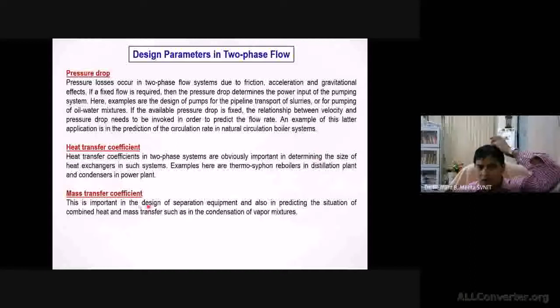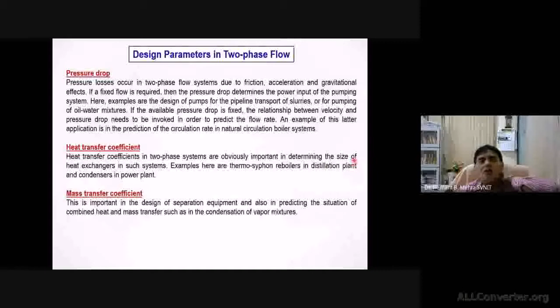The second is the heat transfer coefficient. The heat transfer coefficient for single phase flow and for multi-phase flow are different. The heat transfer coefficient in two-phase flow systems is very important in order to define the size of the heat exchanger in the system. Say, for example, you want to design a condenser or an evaporator. You cannot design the evaporator by considering only vapor, or the condenser by considering only liquid.